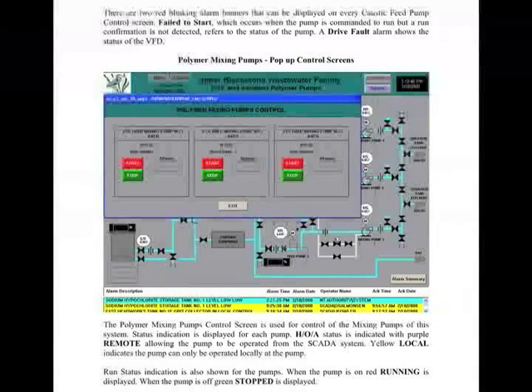On the polymer mixing pumps, which is page 19, we only have start-stop controls. They're either running or they're not. Their hand-off-autos are either in local or remote, and they have fail to run or fault alarms as well.